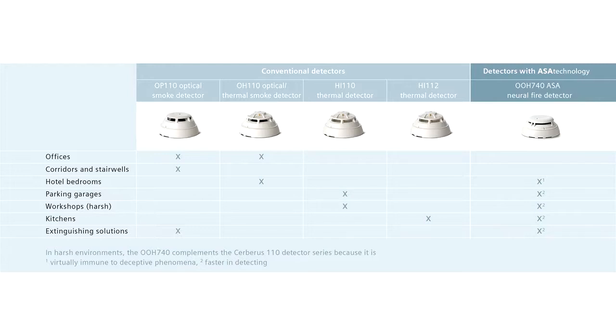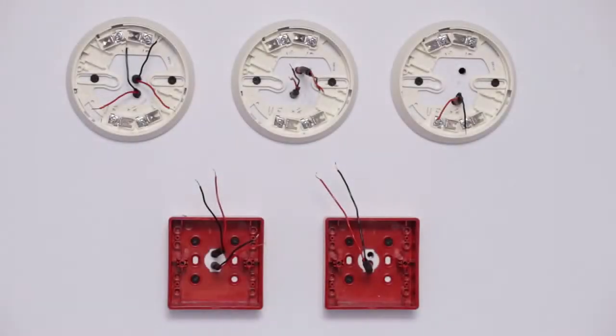The Cerberus 110 detector series includes the highly reliable smoke detector OP110 as well as the rate of rise heat detector HI110 or the static heat detector HI112. Additionally, the OH110 multi-criteria sensor is available, which has a high immunity against transient false alarm causes. Depending on the behavior, you can select parameter sets for sensitive or robust applications. For very harsh environments or in case a fast detection is needed, you can also use the OOH740 neural fire detector. Depending on the selected ASA parameter, it provides you with the highest reliable detection combined with immunity against deceptive phenomena.